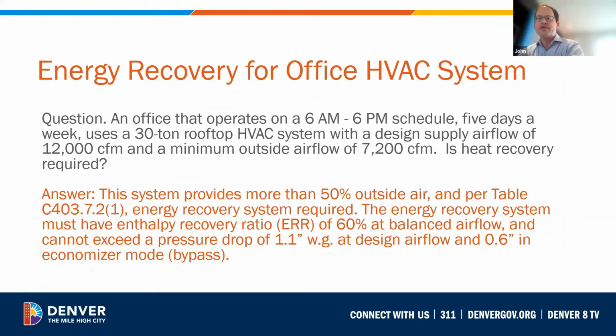This example describes an HVAC system for a building with a 12-hour day, 5-day a week HVAC schedule. The system requires a minimum outside airflow of 7,200 CFM, and it has a design airflow of 12,000 CFM, which results in a minimum outside air fraction of 60%. Since this outside air rate exceeds the threshold for energy recovery, an energy recovery system is required.